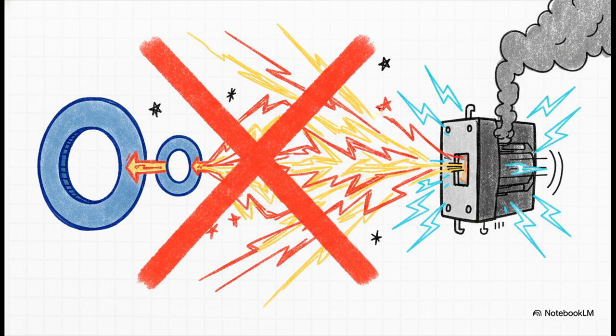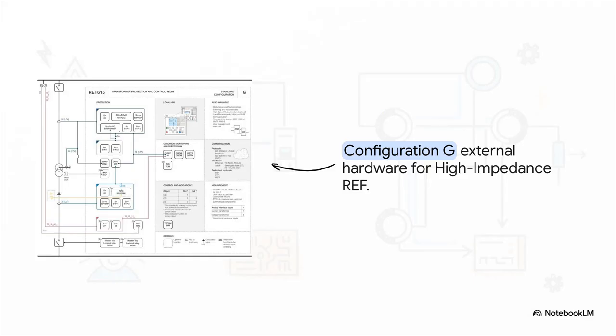If you try to force a high impedance setup onto mismatched CTs just to see if it works, that uncompensated mismatch current has absolutely nowhere to go except right through the relay coil. You're just asking for a false trip or completely damaged components. Now that being said, if your CTs do match perfectly, configuration G for the high voltage side is a great example of this done right. When you implement it correctly, that extra stabilizing resistor gives you extreme sensitivity for faults really close to the neutral point. That raw sensitivity is exactly why it remains such a highly respected utility standard today.